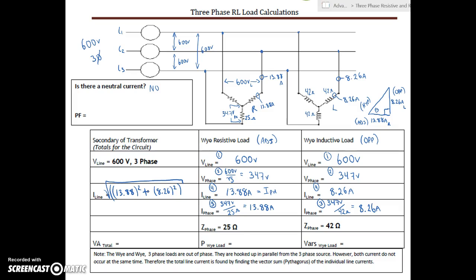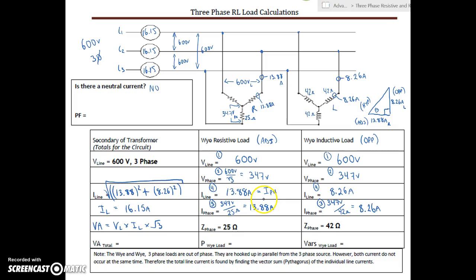Applying Pythagoras gives us a total line current of 16.15 amps. Because both loads are balanced, all three lines carry exactly 16.15 amps. Line 1, Line 2, and Line 3 are all balanced at 16.15A. That completes Step 5 — finding the total line current.